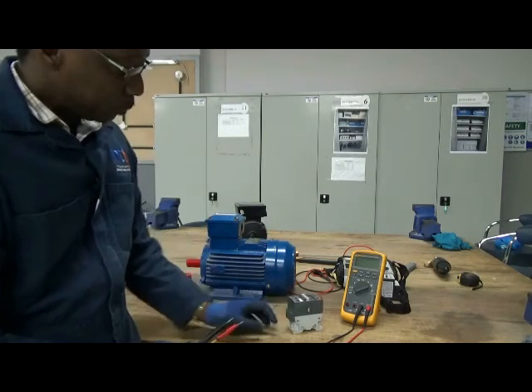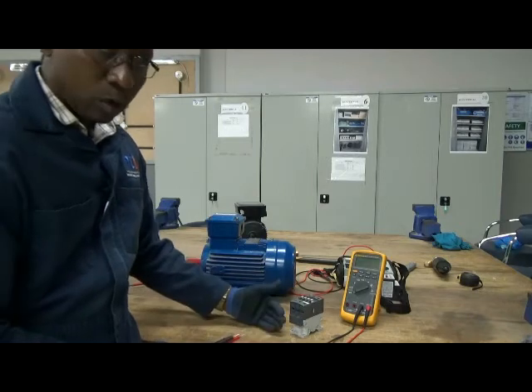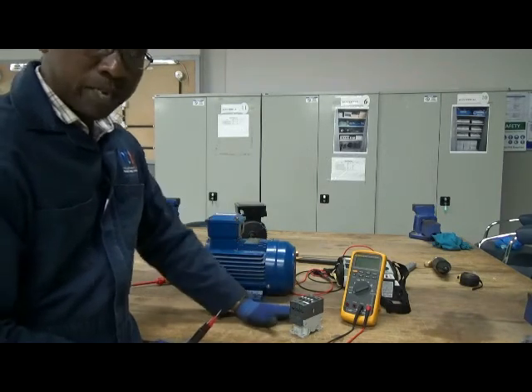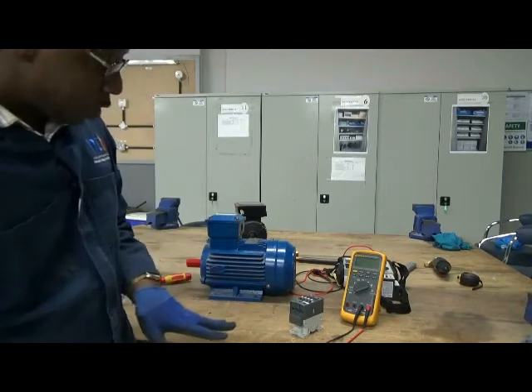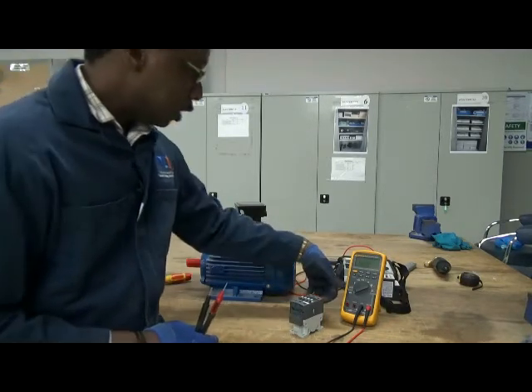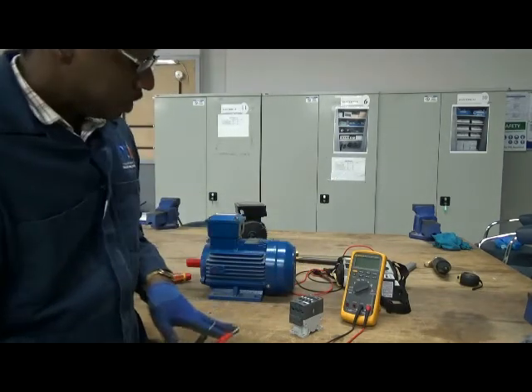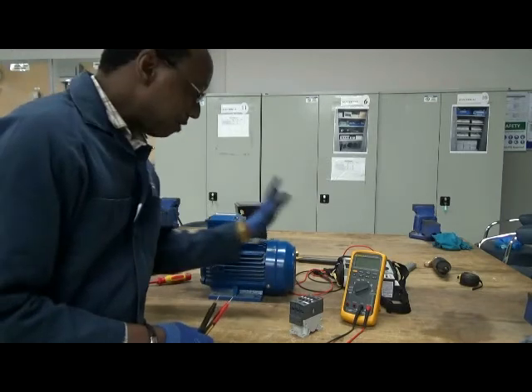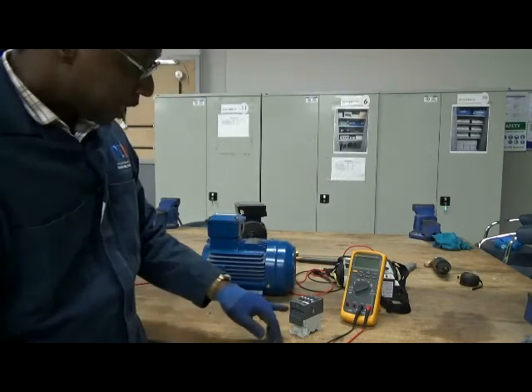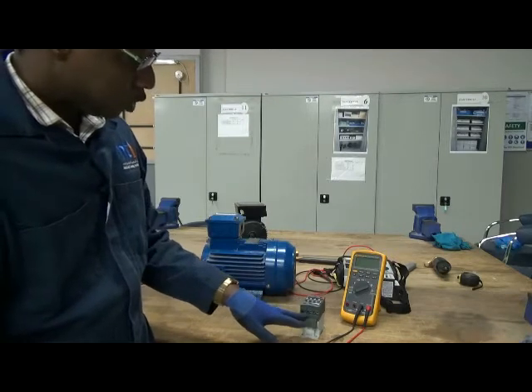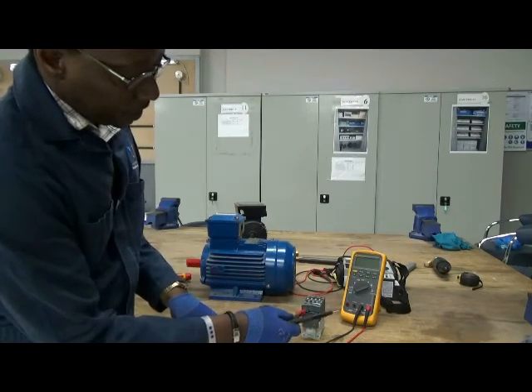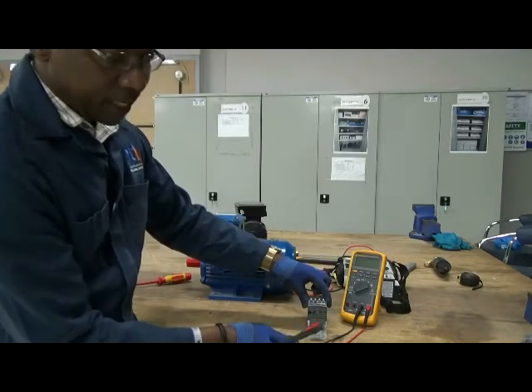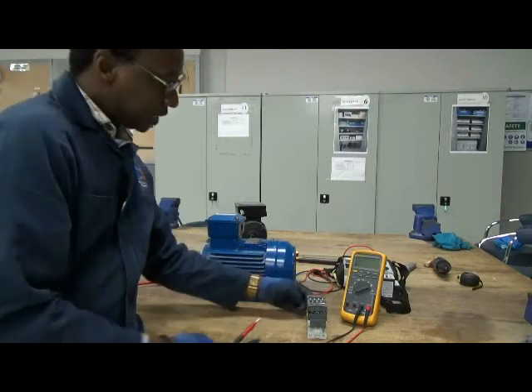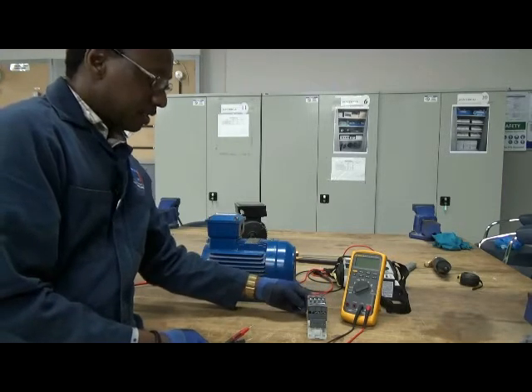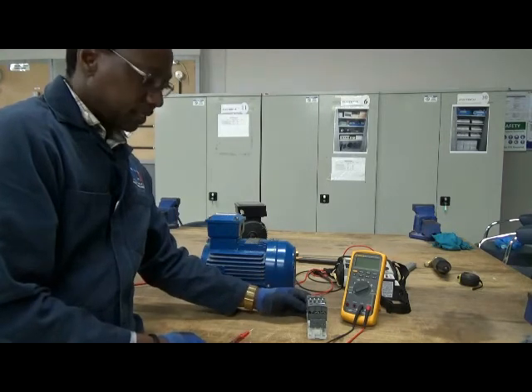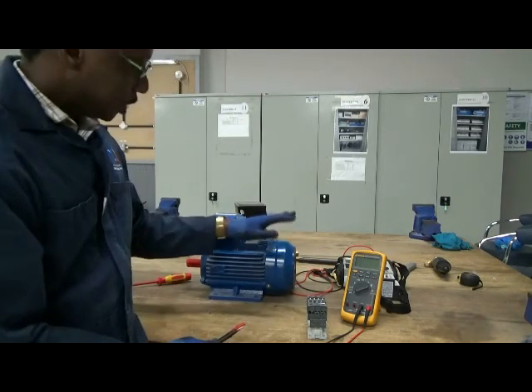So what is happening is I'm just putting a supply here, live and neutral. The coil gets energized and it closes the main contacts. And if I've got power coming in and going out through there, then it means the power can go wherever I'm directing it to. In other words, I'll connect my L1, L2, L3 on those 3 points here, red, yellow, blue, or live 1, live 2, live 3. And on the other side, I'll connect again three other wires going to the machine, for instance, this.